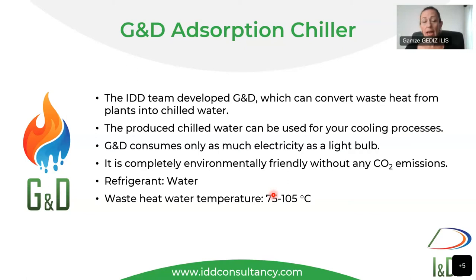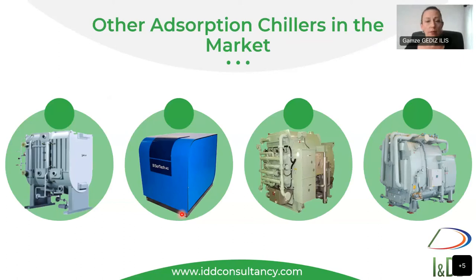If you have waste heat water around 70 to 105 degrees Celsius, we take it and use it inside our adsorbers to generate chilled water. Here are other adsorption chillers in the market. The one on the left is from America — it's no longer on the market and was developed for small villas and houses; it's not working properly. The one on the right is from India — it works, but only at constant temperatures with specific mass flow rates. That's why the application of these adsorption chillers is very limited right now.